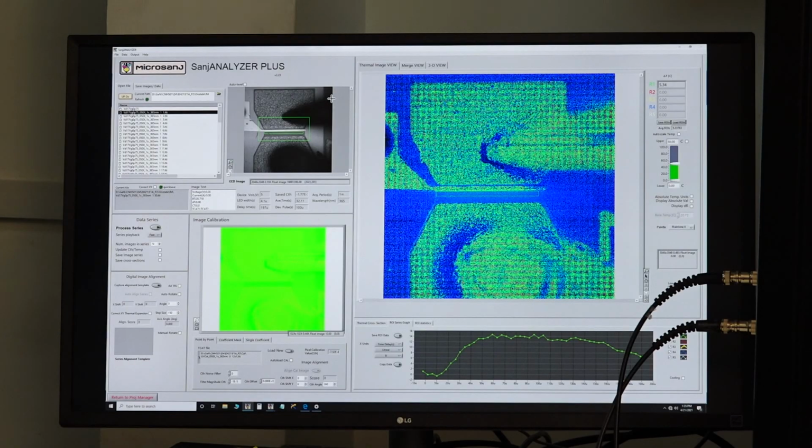So we'll repeat the analysis portion on a transistor transient image that we have captured. First we'll load a calibration image by going to open file, and then we'll go to correct XY to account for thermal expansions. Once we do the XY correction, we go to save images. We select the image save format to TTI, and then we save the corrected calibration image.